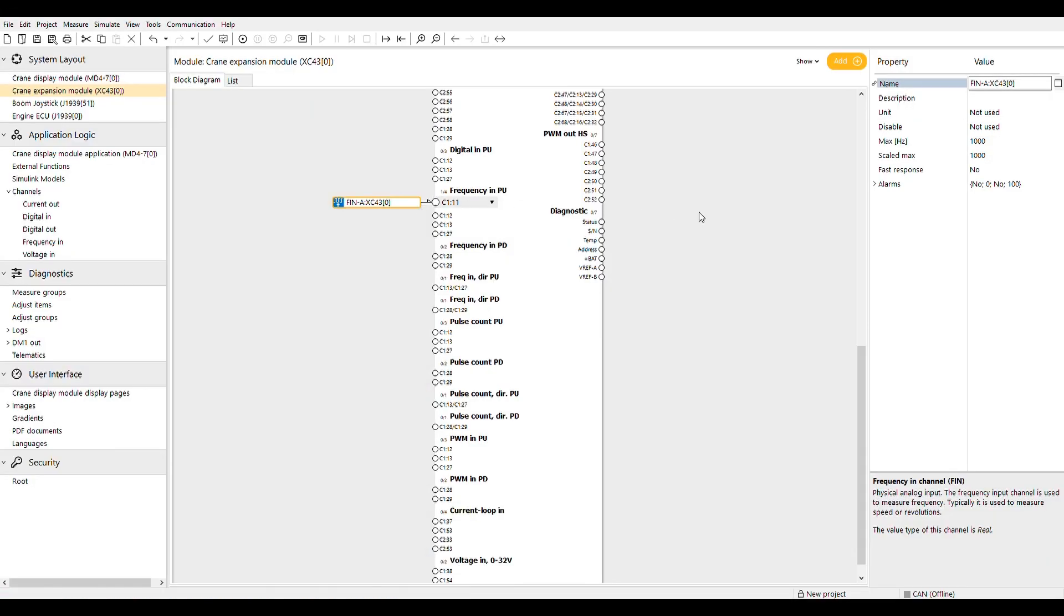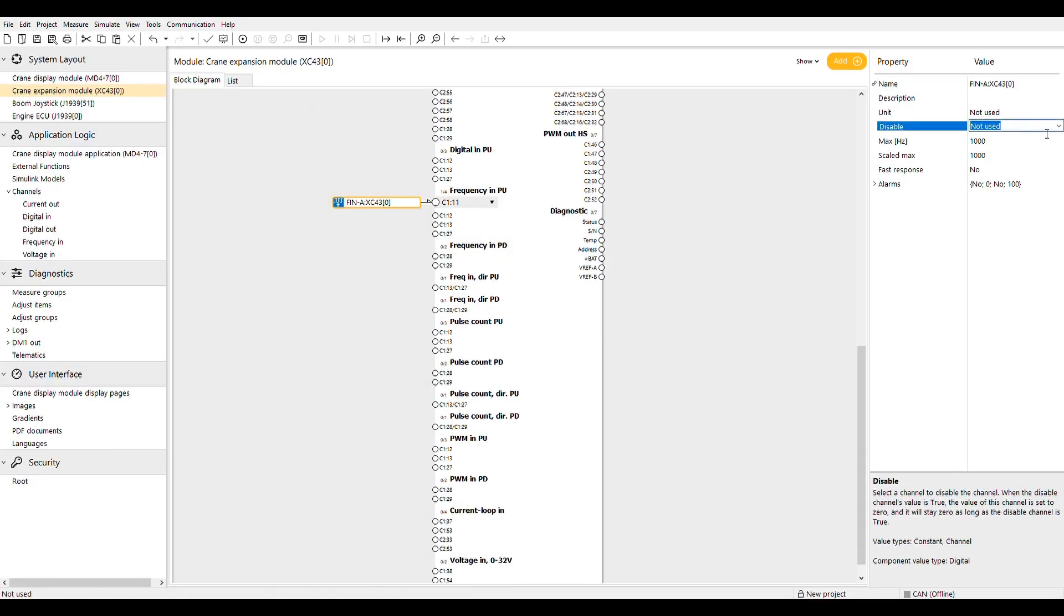Disable is defaulted to not used but can be assigned to a channel in order to allow control over when it's active. In this example, when the door switch is true the frequency input will be disabled.